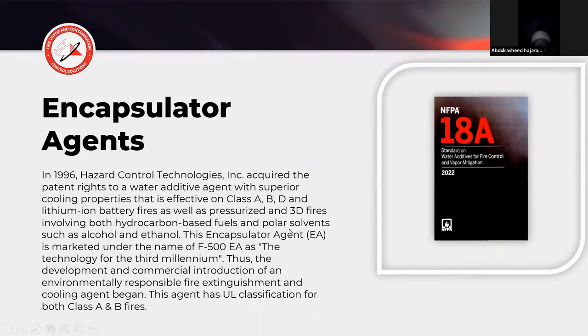But one of the things that I want to key in on right now is again, this 3D fires, because we're all familiar with foam. And if we go into the foam standard NFPA 11 and just go down into Annex A11 of the standard, it's going to show that foam is not suitable for a three-dimensional fire.